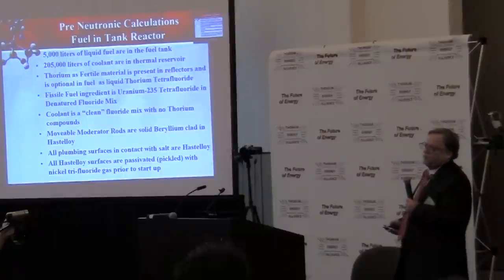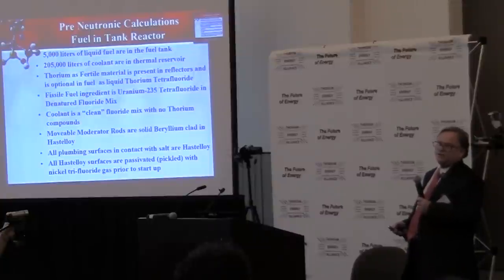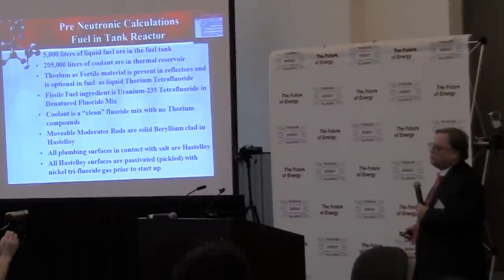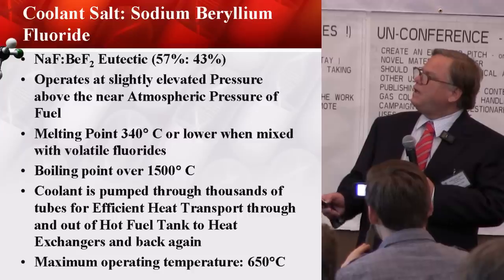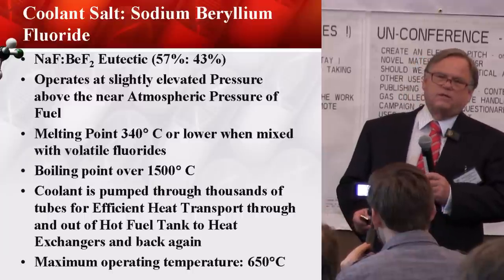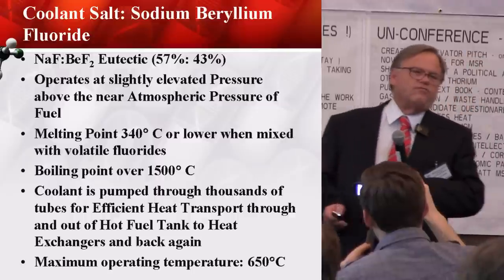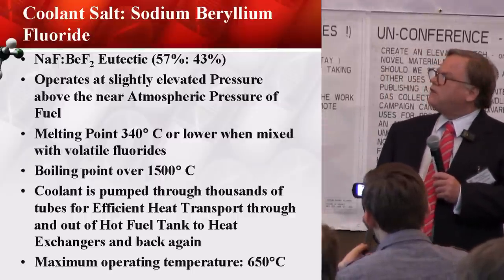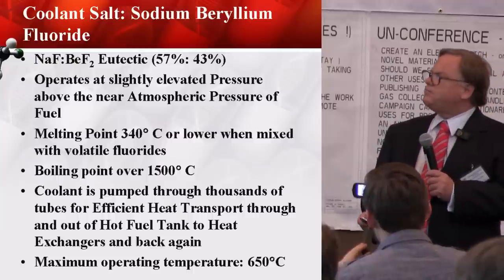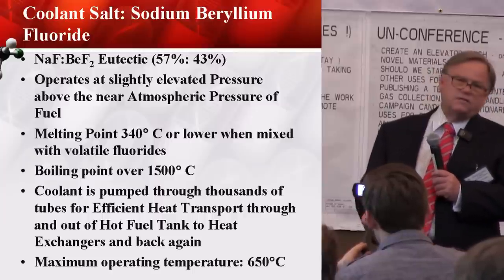Our plumbing surfaces in contact with the salt are Hastelloy, and our Hastelloy is pickled before it's put into service, and that's passivated. That's like anodized aluminum. It puts a little surface on there that hardens the surface against corrosion and cavitation. Well, the coolant is the cheap coolant. I selected sodium fluoride simply because we don't have to spend money separating lithium. We use a eutectic. We can add some more volatile fluorides to this mix to reduce the melting temperature. This may be desirable for some applications. Other applications, no. And the coolant is pumped through the tank.